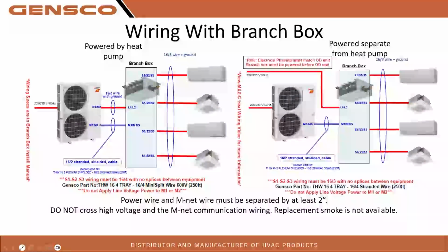Alrighty. So wiring. When it comes to using a branch box, your branch box can either be powered by the heat pump, as you see here, or it can be powered separately from its own power source, its own breaker. Just depending on what's going to be the easier application for you. For the power wire going from your heat pump to your branch box, or from your circuit to your branch box, if you're going from the heat pump, there's a terminal on there called L1, L2, just screw terminals. That is what is powering your branch box.